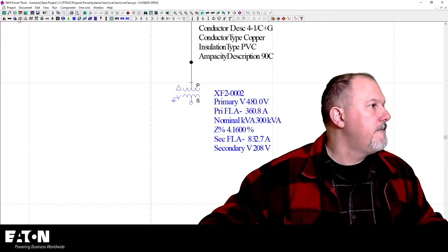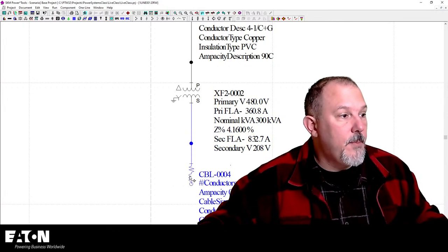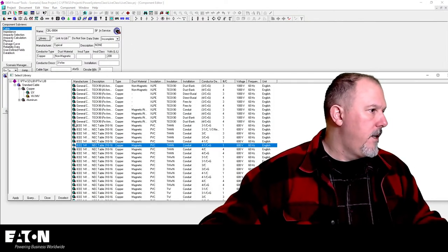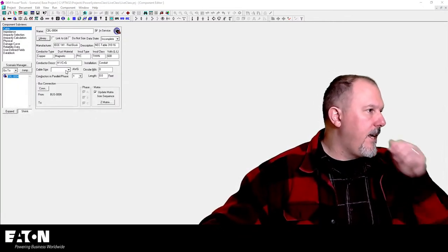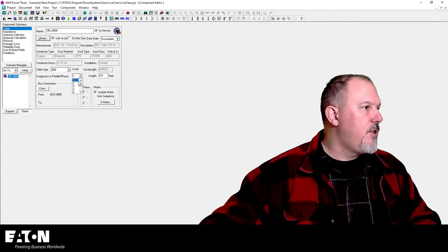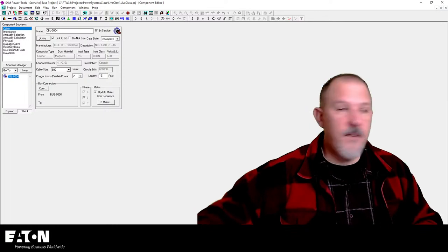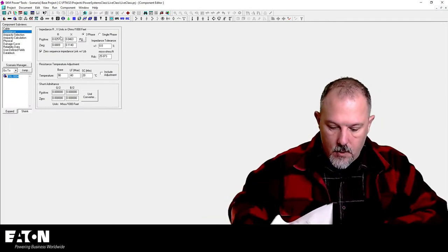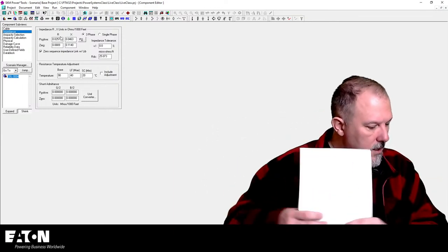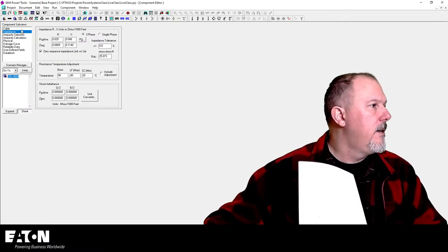Okay, and I'm going to close out of that. Then we have another conductor, and this will be cable 4. Cable 4 is two 600 MCMs. I'll just drop this in. Cable size, two 600s, two in parallel, and 15 feet. I'm going to uncheck the library. Now my resistance for conductor 4 was 0.025, and then the X was 0.048, so instead of 0.0463, I'm putting 0.048. So there's my conductor. I got my length, and I'm going to close that.